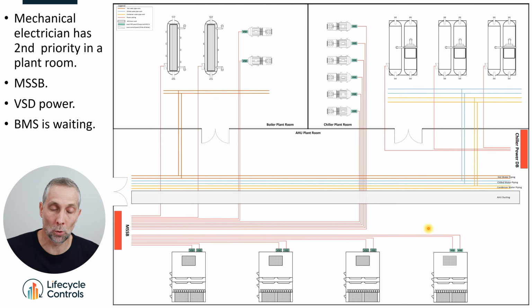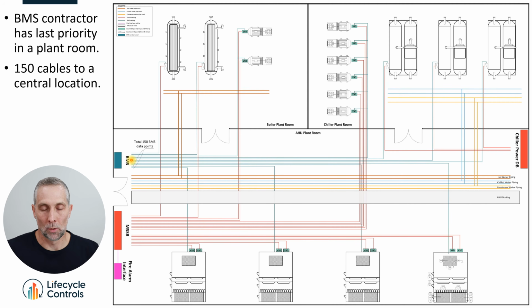Now, sometimes the install contractor will start roughing in some cabling on these air handlers, but the cables will just be rolled up and waiting. They might do some install here and roll up the cables. Maybe in the boiler plant room, start doing some roughing, rolling up the cables, because they can't get these cables all the way down through these common areas, because these common areas are very busy with pipe fitters and people doing the duct and the mechanical electrician. The BMS company does not have priority yet to work in the plant room. The BMS company is normally waiting. And then eventually, when the mechanical has progressed and the mechanical electrical has progressed, then it's the BMS company's chance to work in the plant room.